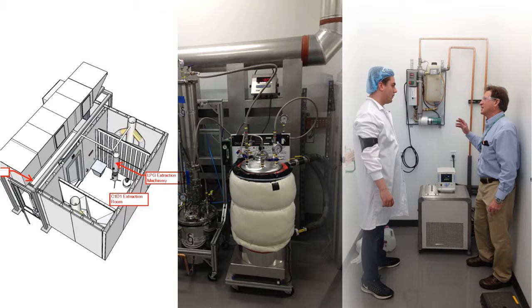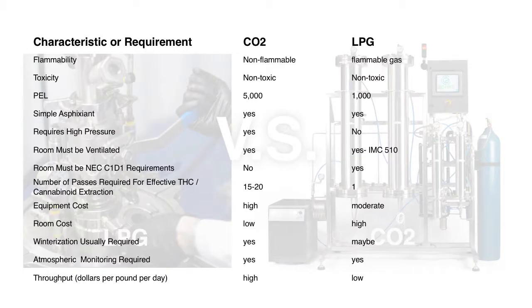So let's go through some of the comparisons and contrasts. I think we have a table here so that the listener can follow. Again, starting off with flammability, obviously CO2, or carbon dioxide, is not flammable, and LPG is. And that, of course, directly impacts the type of facility. If you're going to make a CO2 facility, it does not have to have as much in-depth engineering controls as an LPG facility has. Obviously, we're not going to create a potentially explosive atmosphere. Both of these are non-toxic. They're what we call simple asphyxiants. They displace oxygen.